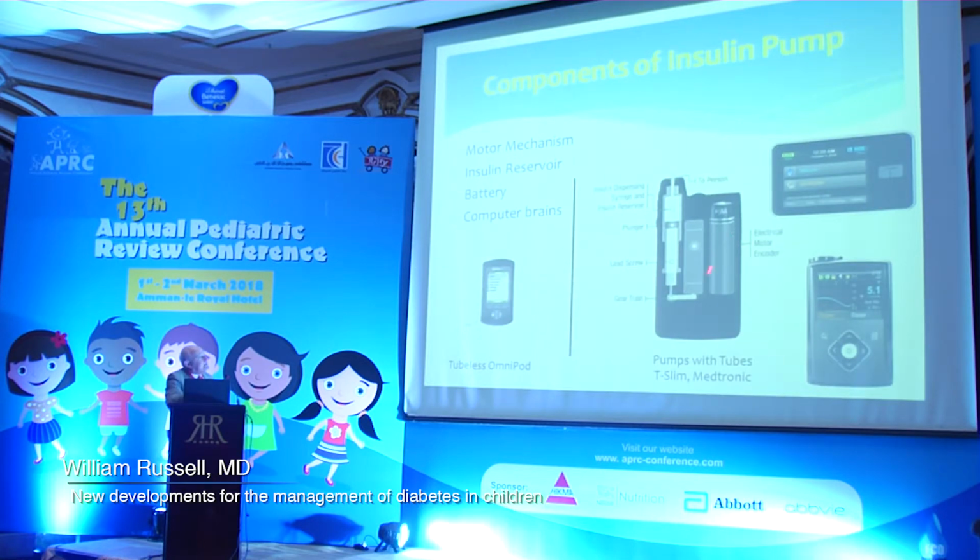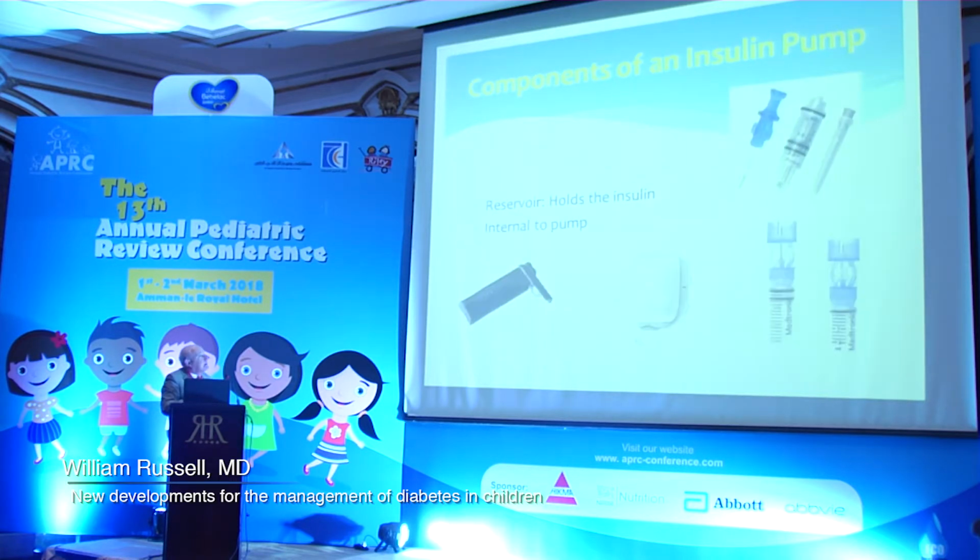Inside of a pump is something like this, a reservoir that contains anywhere up to usually about 300 units, some pumps less than that, down to 180 units of insulin, a motor, a battery, and a computer chip that really drives this. There's some examples of reservoirs.